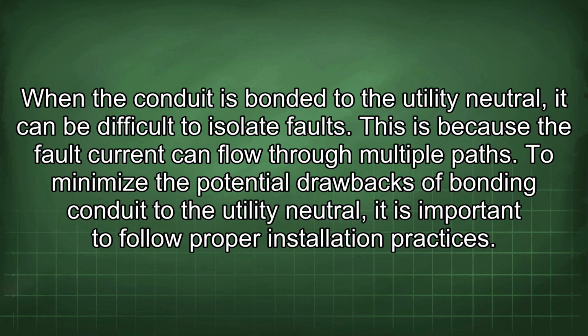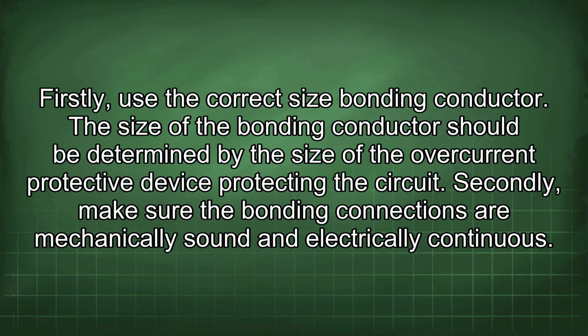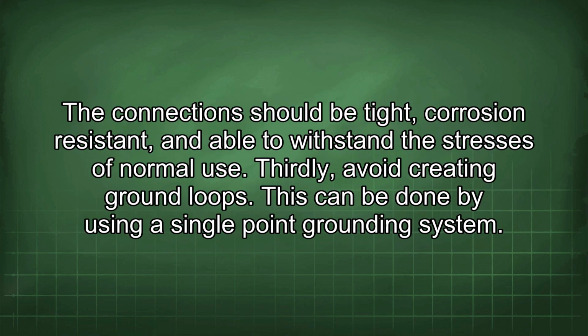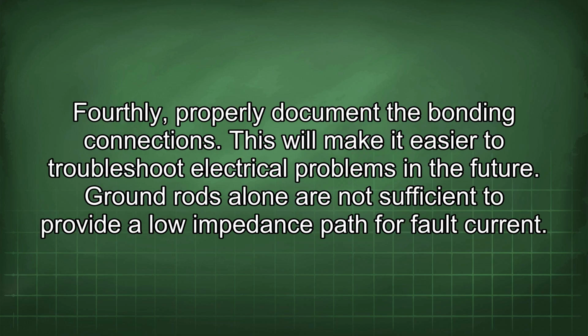To minimize the potential drawbacks of bonding conduit to the utility neutral, it is important to follow proper installation practices. Firstly, use the correct size bonding conductor. The size of the bonding conductor should be determined by the size of the overcurrent protective device protecting the circuit. Secondly, make sure the bonding connections are mechanically sound and electrically continuous. The connections should be tight, corrosion-resistant, and able to withstand the stresses of normal use. Thirdly, avoid creating ground loops. This can be done by using a single-point grounding system. Fourthly, properly document the bonding connections. This will make it easier to troubleshoot electrical problems in the future.